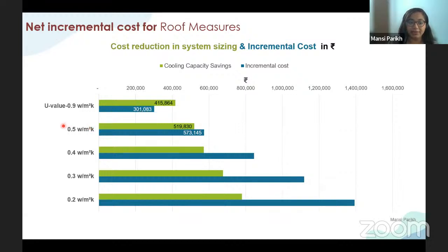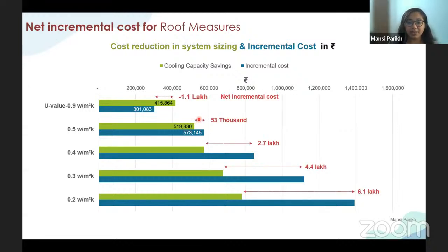Similarly, to achieve a U value of 0.5 watt per square meter Kelvin, the incremental cost is 5.7 lakh. However, the cooling capacity savings it provides during the selection of the equipment is 5 lakh rupees. So your net incremental cost is the difference between both of these. In this case, for a U value of 0.5, your net incremental cost is 5.7 lakh minus 5.19 lakh, which is around 50,000 rupees. So that is going to be your net incremental cost.